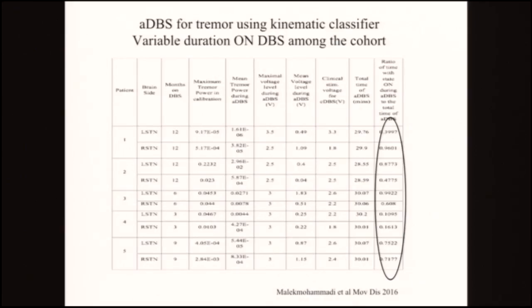So one of the most interesting things across the group, which these numbers are probably too small for you to see, is the percentage of time or the percentage of power compared to if the stimulator had been on for the 30 minutes that were used. And you went from basically 11% to 99%. So the take-home message here is we shouldn't be doing a one-size-fits-all therapy for everybody. This person, depending on how much bradykinesia and rigidity they have, may need some low-lying, adaptive DBS based on their neural rhythms, and then a kick-in every time, with something else, maybe a different frequency. And then there may be somebody who, even with tremor, needs this on all the time.